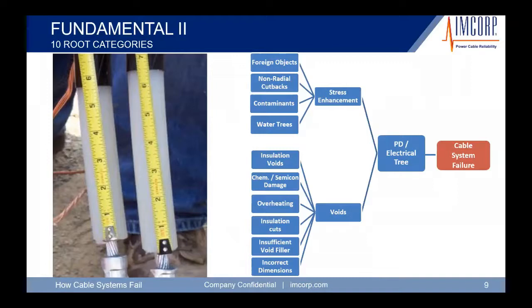But it has to sit right over this area because what it's doing, as we talked about earlier, is terminating the electrical stress that's in those cables. If you hit the wrong dimension, you can completely miss the stress control area and put that just on the insulation, and you don't terminate that electrical stress. So obviously that's going to cause an issue because all you're doing is really insulating this cutback.